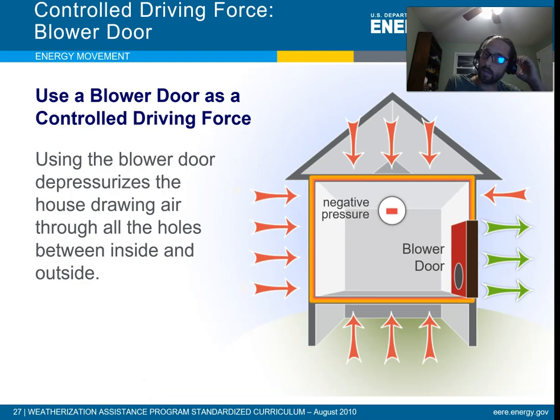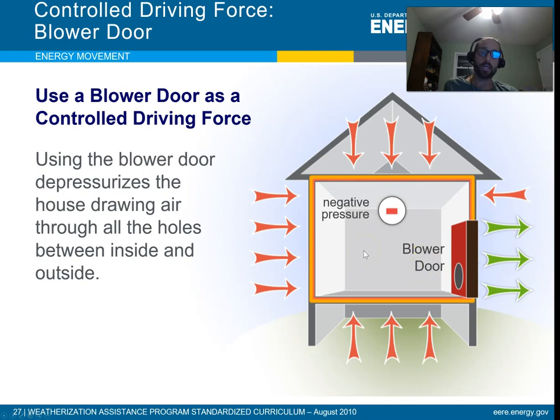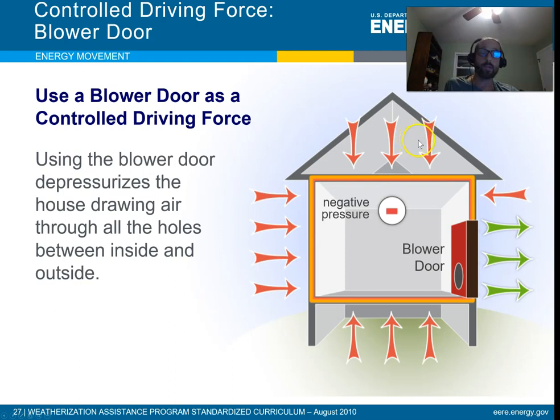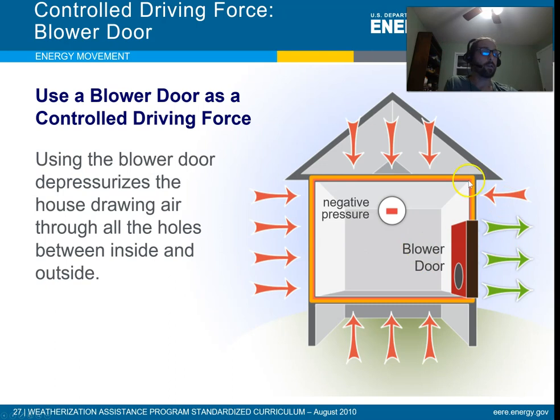In energy auditing, an important tool is the blower door — a giant fan placed in an exterior doorway that depressurizes the building. This creates a large negative pressure zone, forcing air in through all the little direct and indirect leakage areas, which helps identify leaky spots in the building. It can also help identify missing insulation and sometimes water damage.